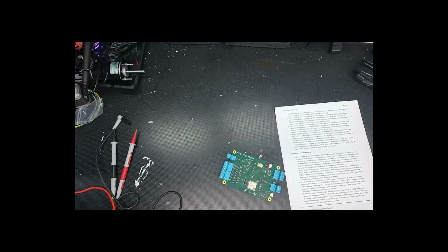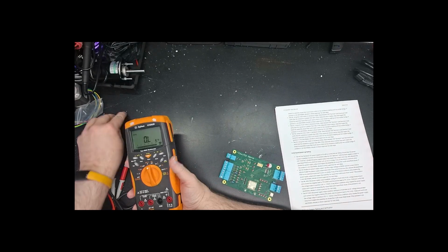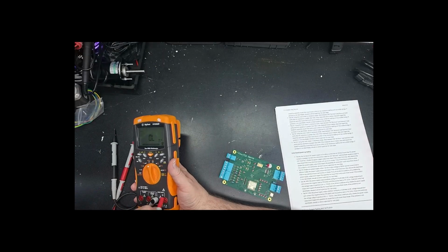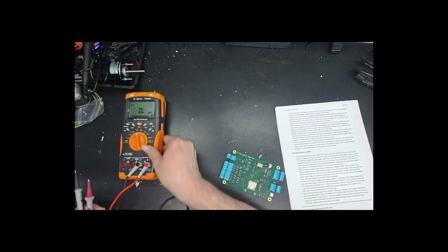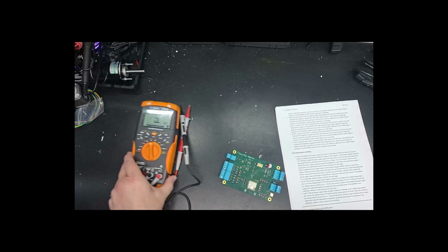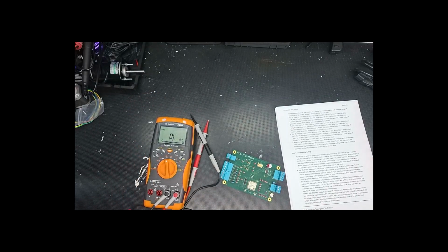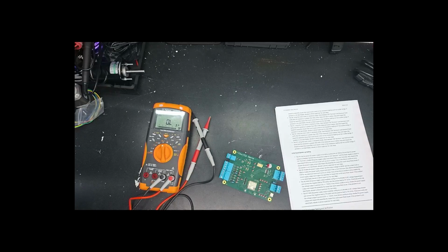So to let you know, I can always throw this in the resources, but the company is local to me here in Ohio. To us here in Ohio, it's Total Calibration Solutions. Just in case you're out in this area, Northeast Ohio. Really good company. You can mail stuff into them. Just keep in mind, calibration is not cheap. It is expensive because there's a lot of expensive equipment involved in calibration. And even the calibration equipment has to be calibrated. So it has to be sent out to a special lab to be calibrated, typically an actual NIST lab.